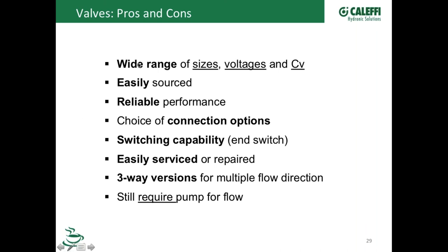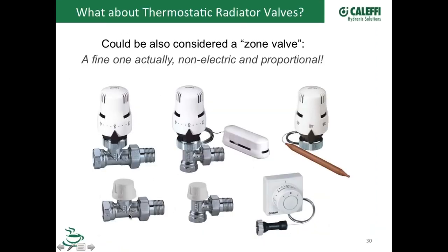But we talked about valves again, a wide range of sizes, voltages, Cv, we talked about that, fairly easy to find. Ours, you can read the heads on the Z1 valves, you have to replace it. That's typically the fail point on the valve, the motor operator, not the valve body itself, other than that one that was limed up that I showed you earlier. End switches on them, easy to repair, three-way versions. I think we probably hit on all that. Now, one other valve that we offer a selection of is a thermostatic radiator valve.